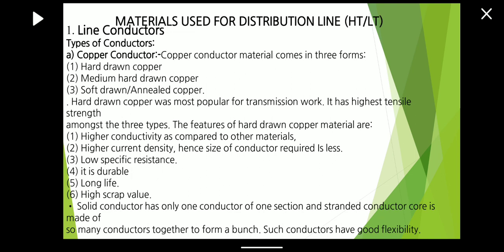Hard drawn copper has the highest tensile strength among the three types. Its features are: higher conductivity compared to other materials, higher current density — hence the size of conductor required is less — low specific resistance, and it is durable with long life and high scrap value. A solid conductor has only one section, whereas a stranded conductor core is made up of many conductors together to form a bunch. Such conductors have good flexibility.